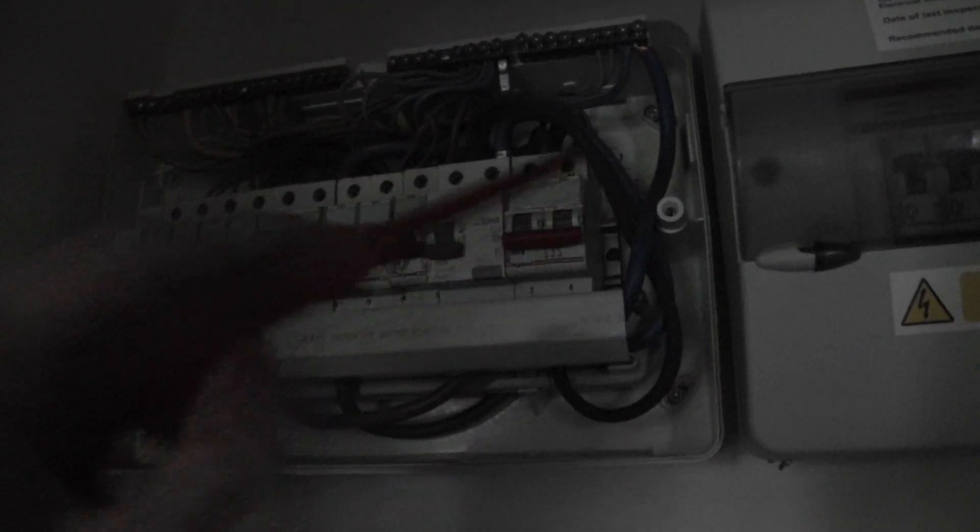Because the RCD reads your difference between your live and your neutral, and if it detects a difference, a 30 milliamp difference, it switches it off. They're really sensitive.